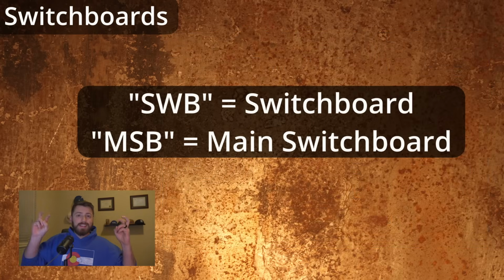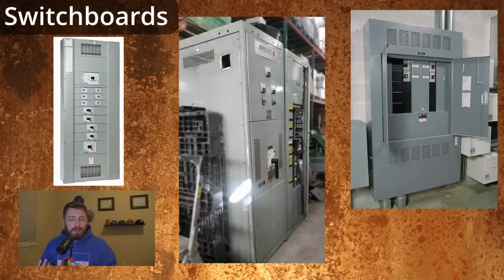A step larger is what we're going to call a switchboard. You'll probably see this abbreviated as SWB, or MSB for main switchboard, if it's the main switchboard for a facility. These are typically found in larger commercial and industrial applications requiring more power. In general, switchboards are three-phase, 208 volt or 480 volt, and rated for anywhere between 600 to 2000 amps. Again, sizes will vary a little bit outside of that, bigger and smaller.